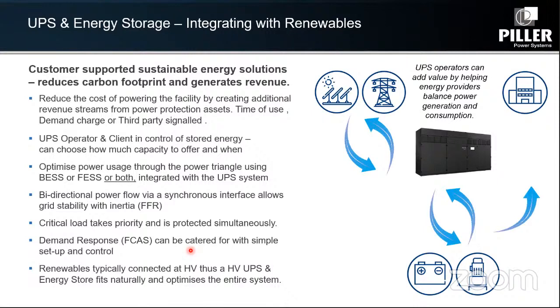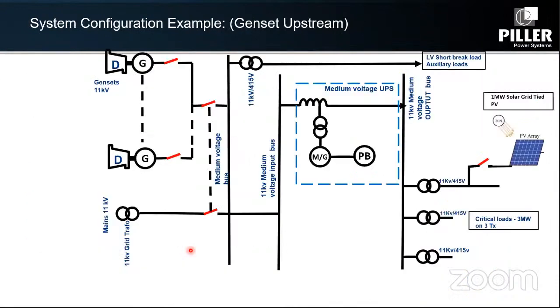I'll tell you a bit about medium voltage, because we already have 3 sites running for the IT space in India. To give an overview of what the previous slide said, here's a simple example — we can have various configurations. What we're showing is a 3 megawatt medium voltage UPS, with upstream standard 3 megawatt gensets, a grid connection coming in, and the customer. This is standalone, of course; in a data center you could have various kinds of redundancy.